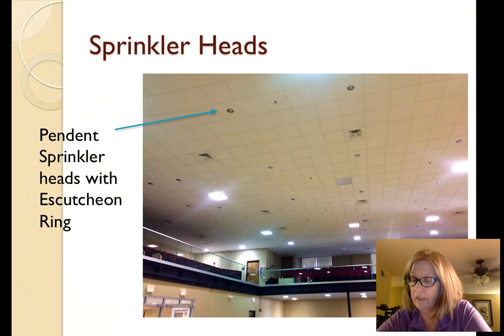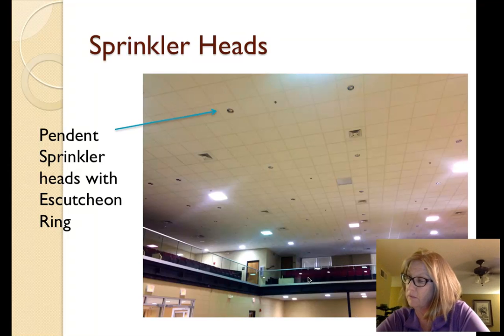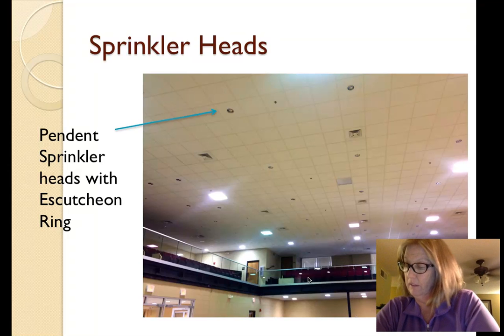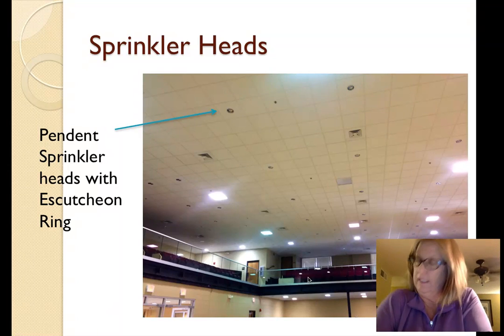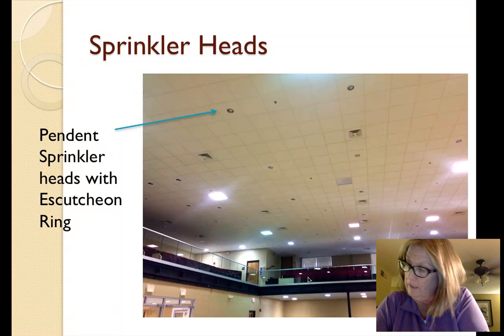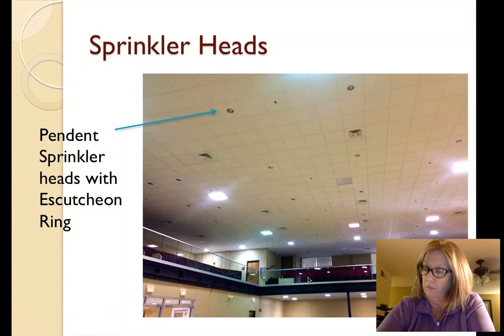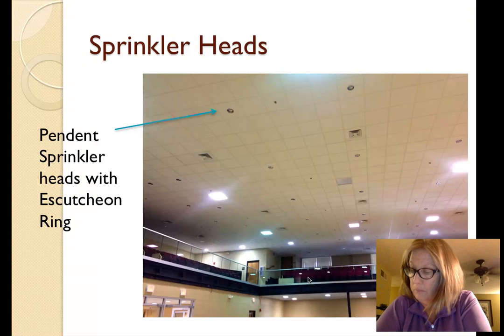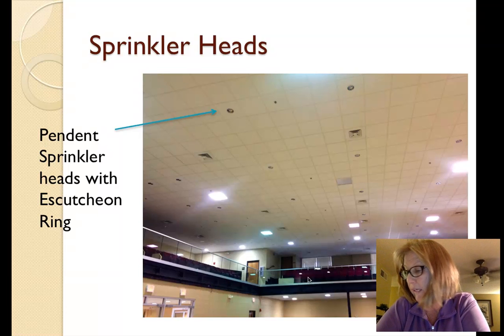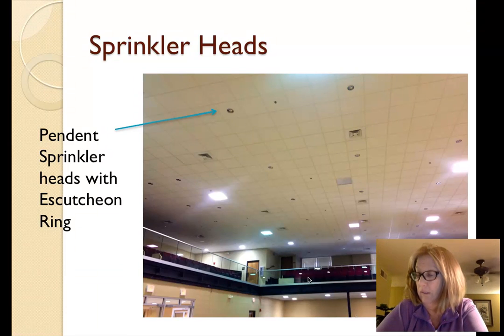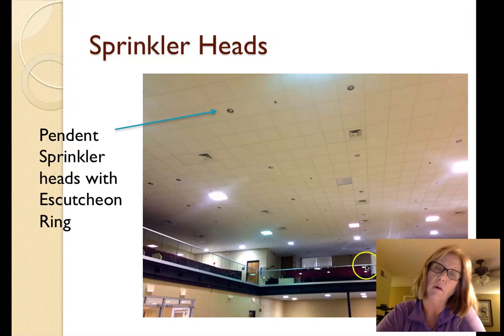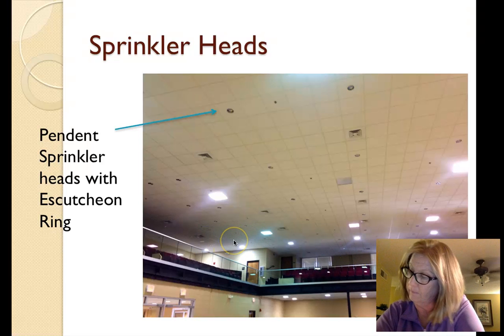So low-hanging areas within the ballroom had concealed sprinkler heads, and the sprinkler heads in the higher ceilings were pendant sprinkler heads with an escutcheon ring. Inspector Ellsworth was pointing out that the concealed plate is soldered and melts at 135 degrees Fahrenheit, and the sprinkler bulb, which is red, is broken at 155 degrees Fahrenheit. This is all per NFPA 13 standard.